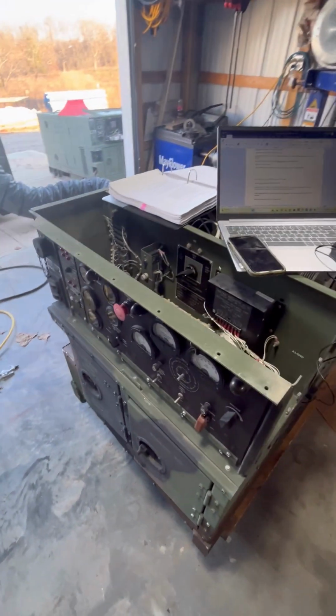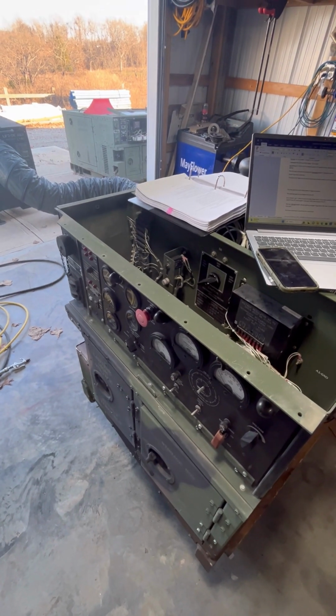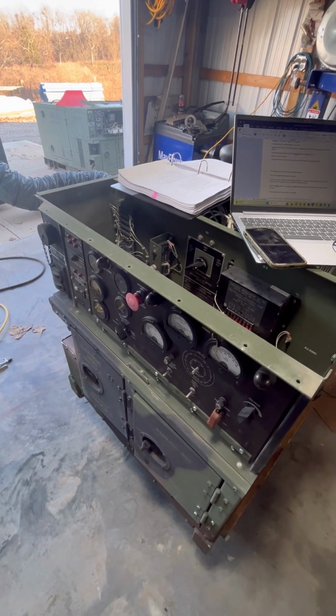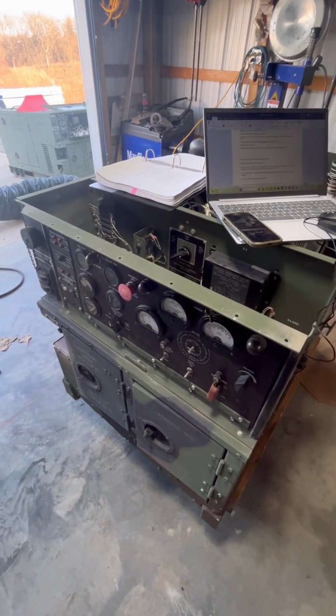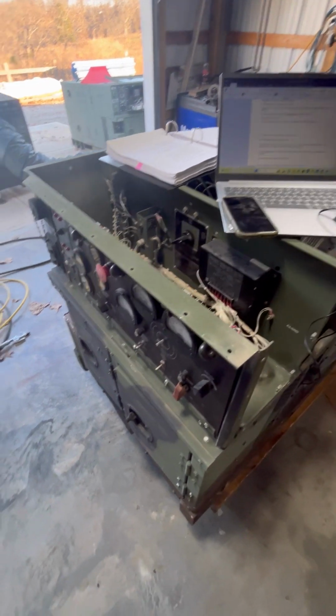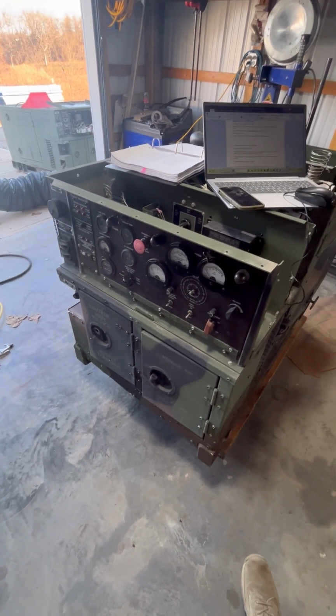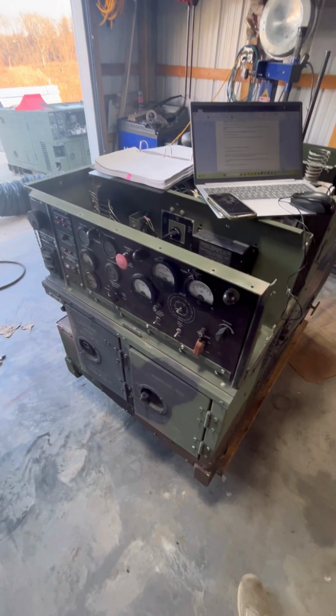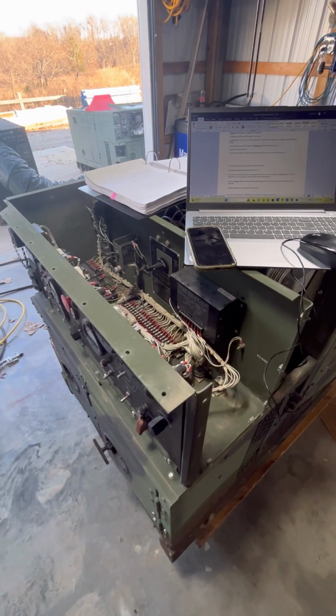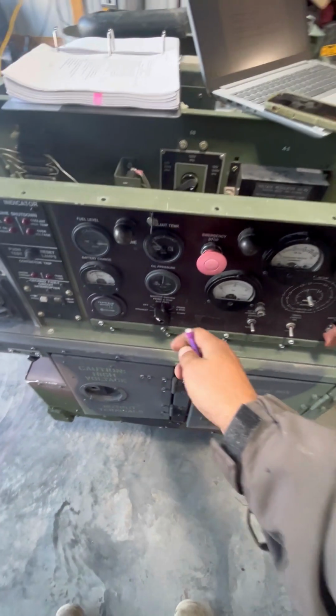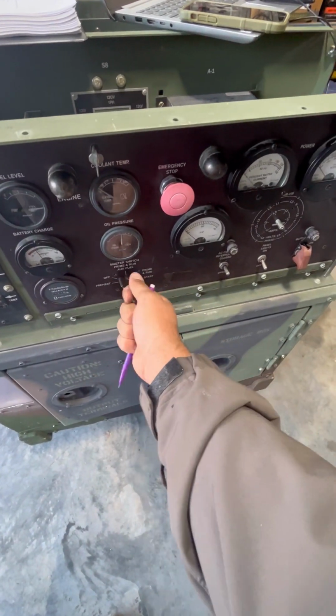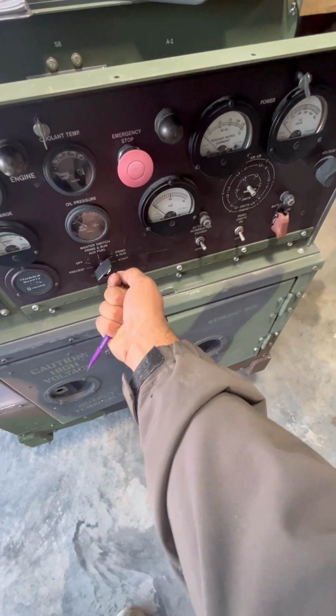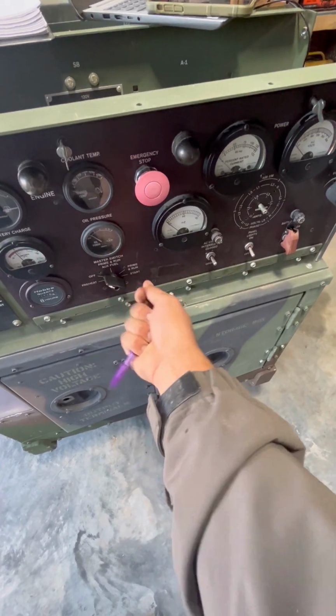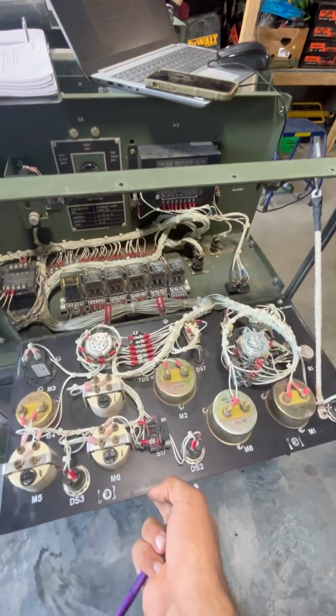And so I did a bunch of reading this morning. I got on Steel Soldiers, and as I was reading, one of the guys mentioned that the main generator can only make power if it gets excitation, and the main generator gets its excitation from the main switch right here. As you hold it to start, when you're in the start position, that's when the generator field gets excited.